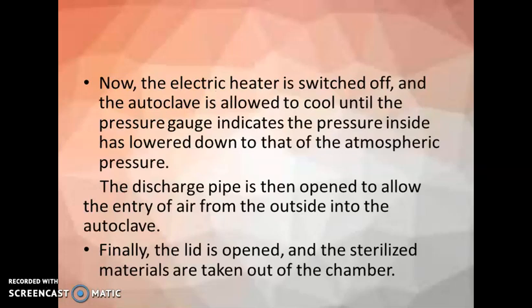After attaining the temperature of 121 degrees Celsius at 15 lbs for the 15 minutes holding period, we can switch off the electric heater and the autoclave is allowed to cool until the pressure gauge indicates that the pressure inside has lowered. The pressure gauge, by measuring, shows the pressure has come down below 15 lbs until it is equal to the atmospheric pressure. Then the discharge pipe is opened, which allows the entry of air from the outside into the autoclave. Finally, we open the lid and the sterilized materials are taken out of the chamber.